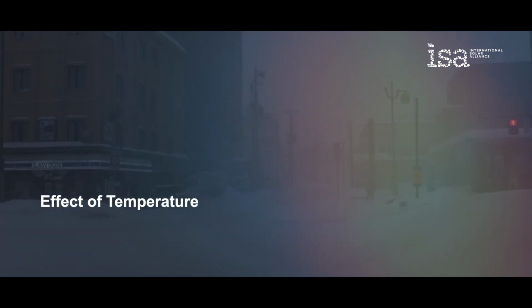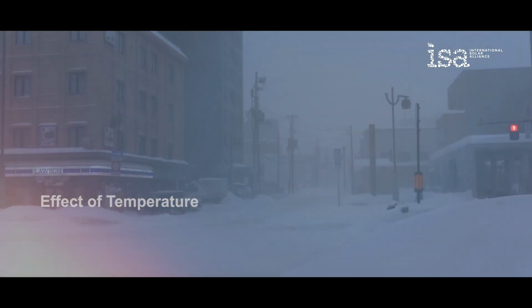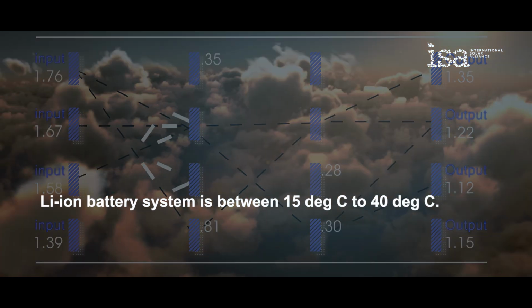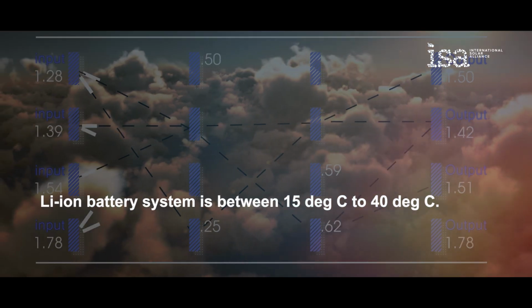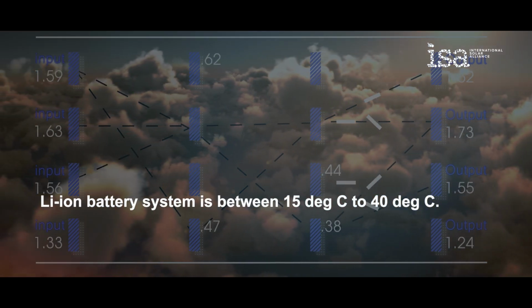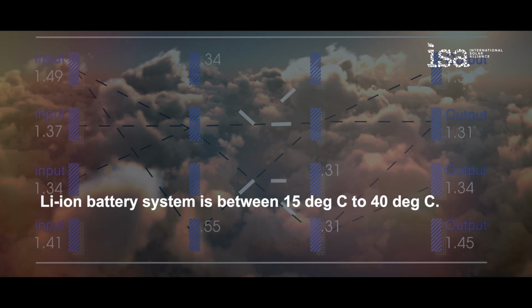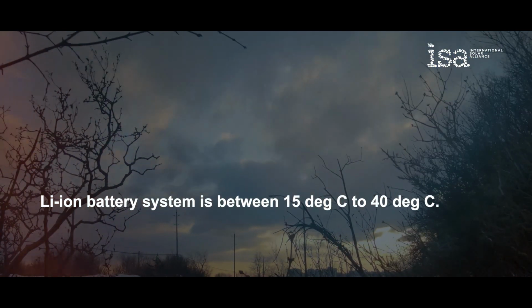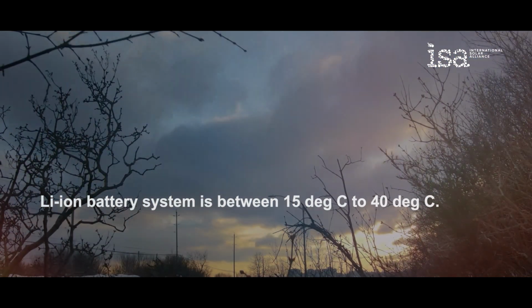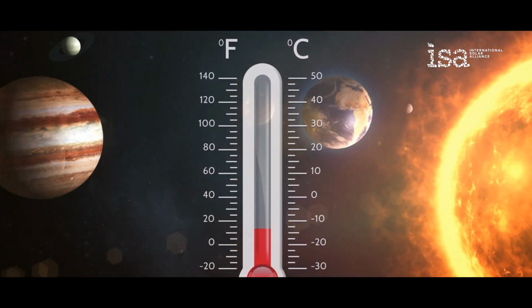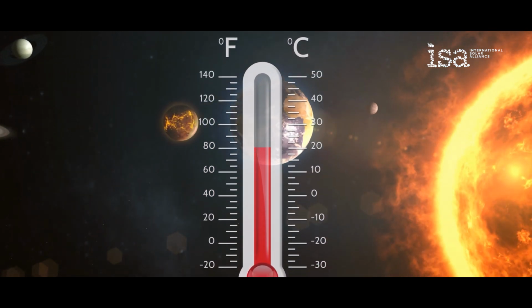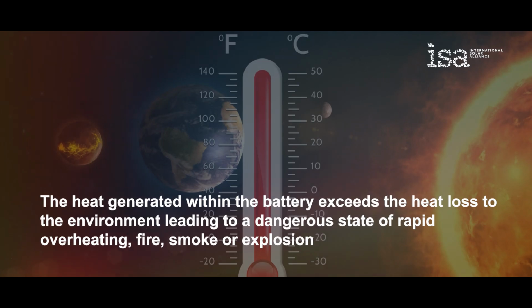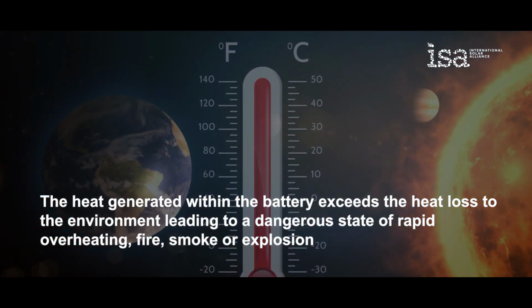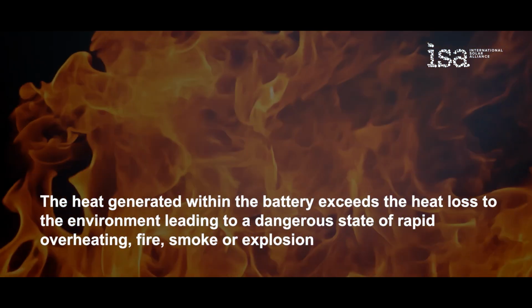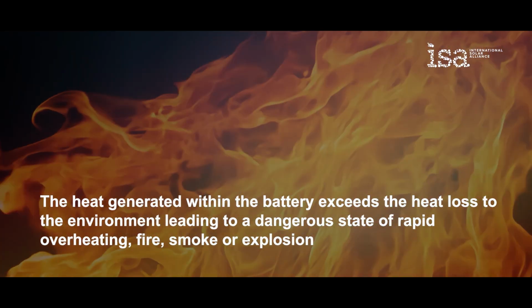Effect of temperature: extreme temperatures can impact the performance and lifespan of the BESS. The ideal ambient temperature for a lithium-ion battery system is between 15 and 40 degrees Celsius. Operating outside this range can negatively affect performance and lifespan. Extreme cold slows ion movement, while high heat accelerates degradation and increases the risk of thermal runaway, meaning the heat generated within the battery exceeds the heat loss to the environment, leading to a dangerous state of rapid overheating, fire, smoke, or explosion.